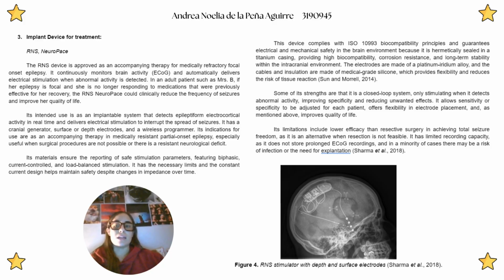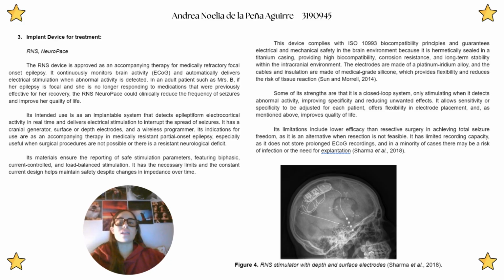Its materials include a titanium hermetic case for corrosion resistance, platinum-iridium electrodes, and medical grade silicone insulation, all ensuring biocompatibility and long-term safety. The key strengths are its personalized stimulation, improved quality of life, and reduced adverse effects compared with open-loop devices. Limitations include lower effectiveness than resective surgery, limited data storage, and potential infection risks.